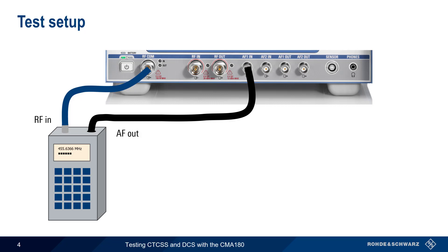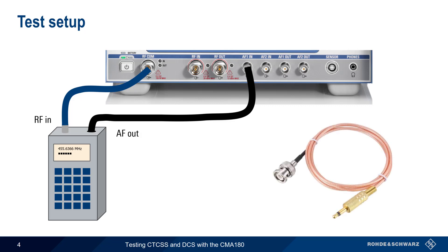The CMA180 audio frequency inputs are BNC connectors, so it's likely that a special cable or adapter will be needed to interface with the receiver's audio output — for example, a BNC to 3.5mm cable. Once the radio is connected, it should be tuned to the desired frequency, and audio output should be set to approximately mid-range.